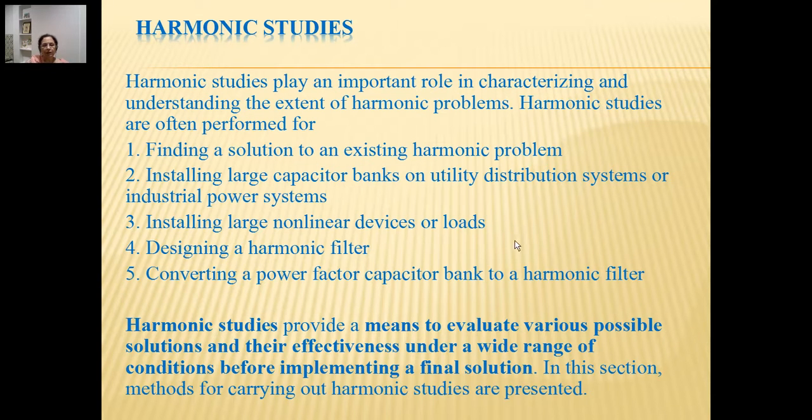Installing large nonlinear devices or loads. The previous operating condition of the system is known from the harmonic study, and if we have to install a large nonlinear device or load, its effect on the operation of that part of the network can be studied first. Then, by doing an appropriate study and checking against the available standards, it can be decided whether the harmonic content, which may increase because of large nonlinear devices, is within the permissible limits or not. So for that, harmonic studies are very important.